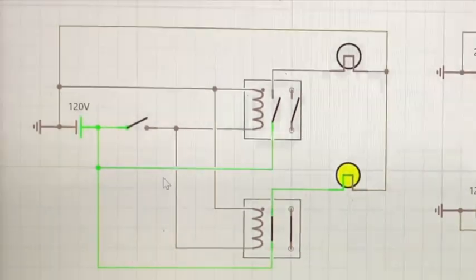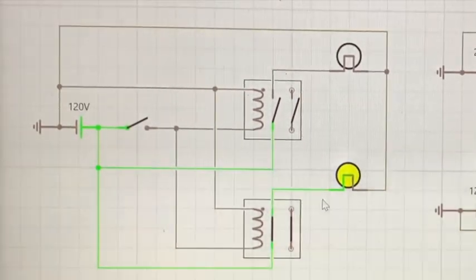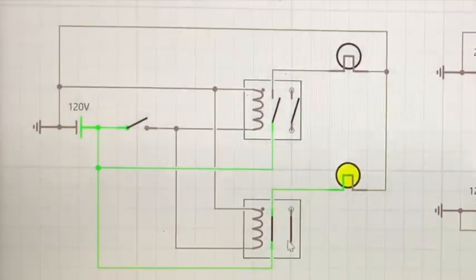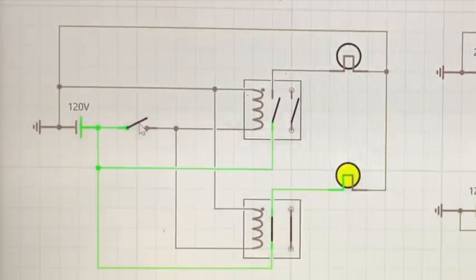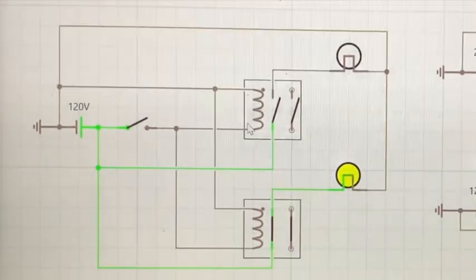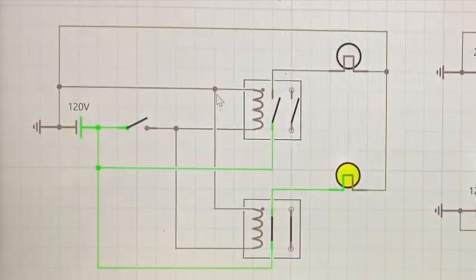At the same time, because remember the relay we saw had two, had a normally open and normally closed function. This one is normally closed, this one's normally open. When I add power, the voltage is going to go to the coil. As long as our neutral is hooked up, this is actually going to magnetize and close this circuit.